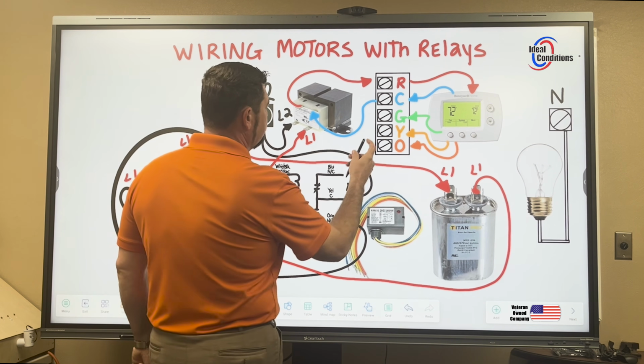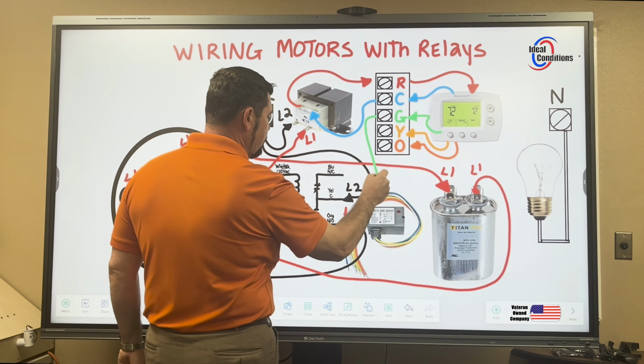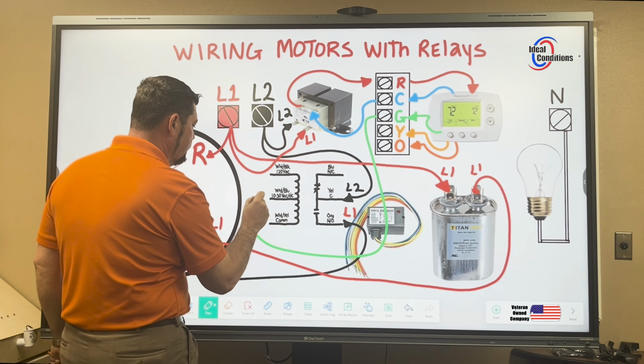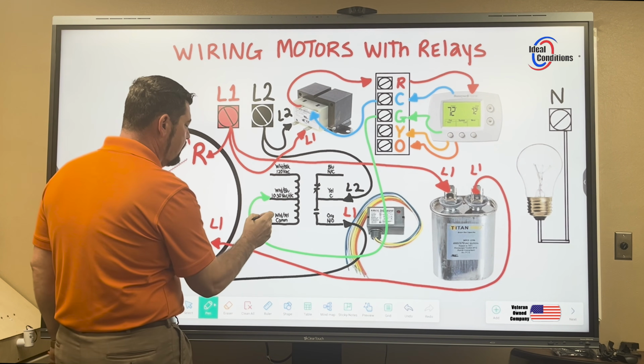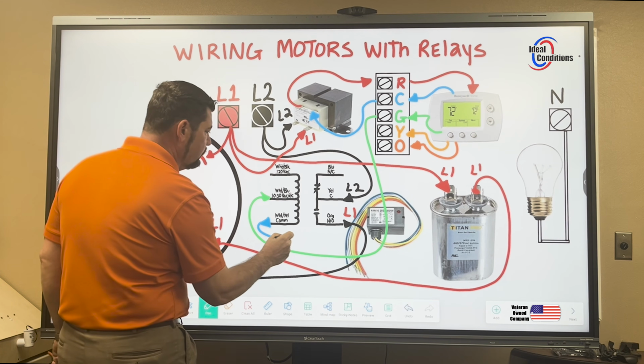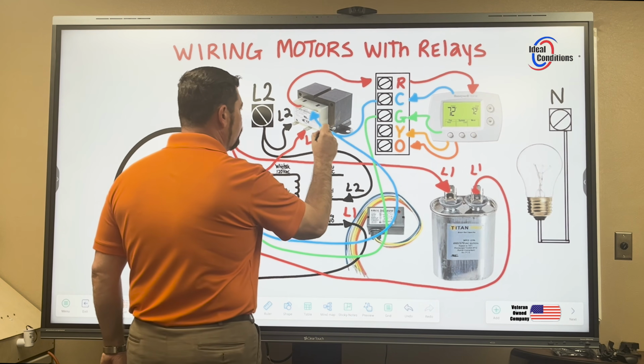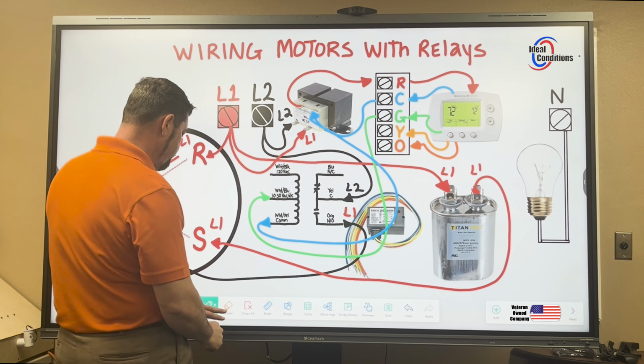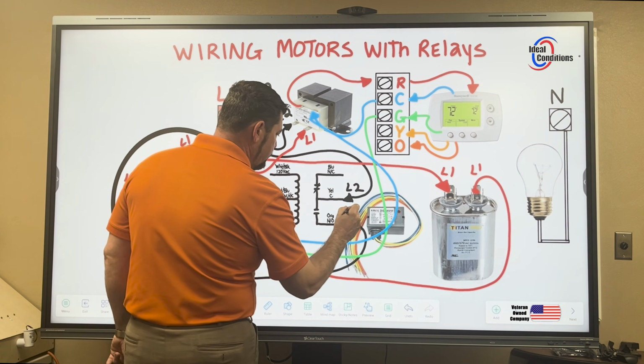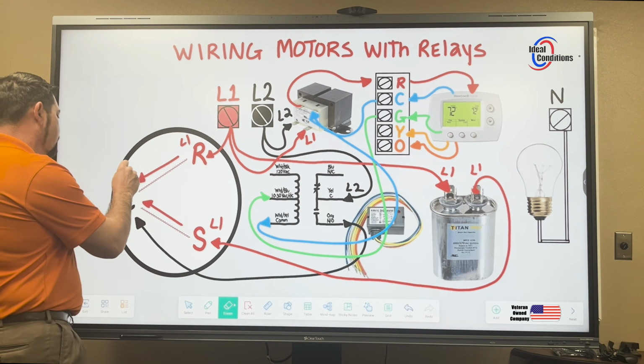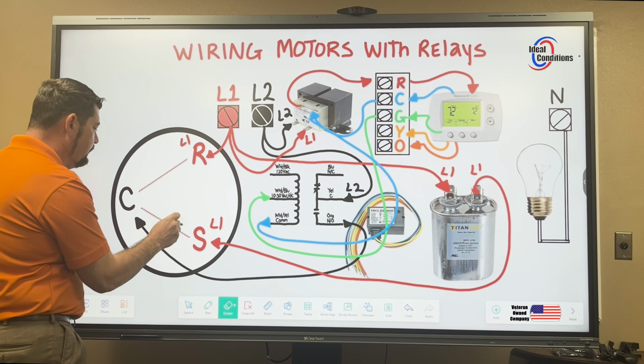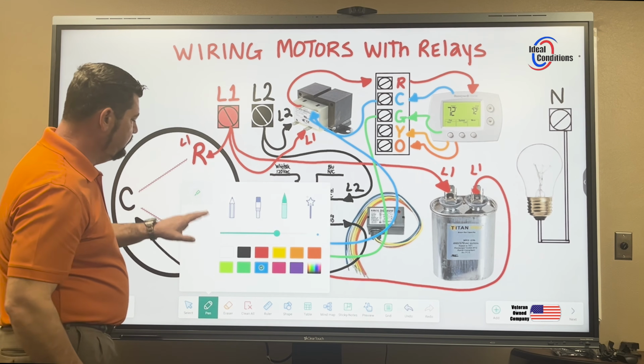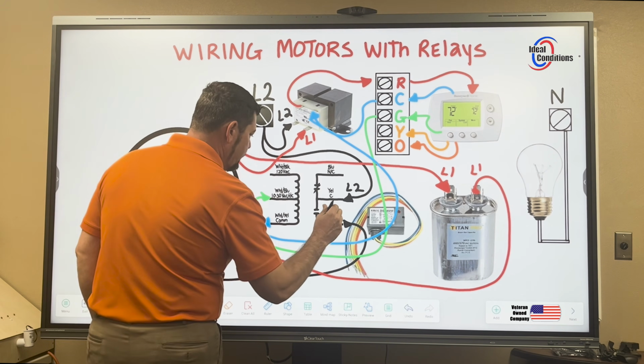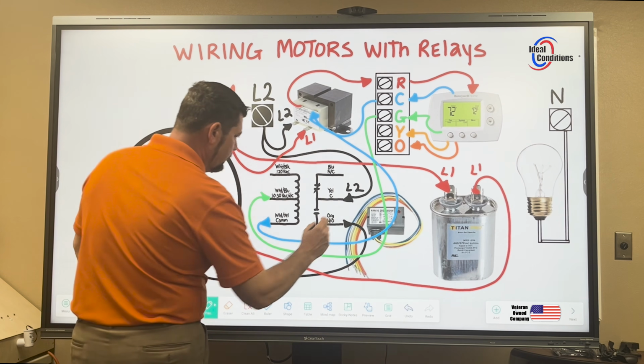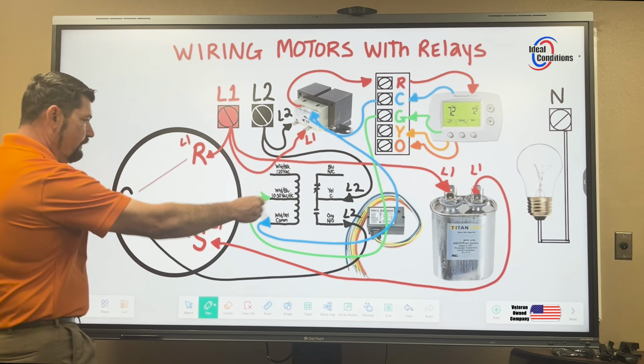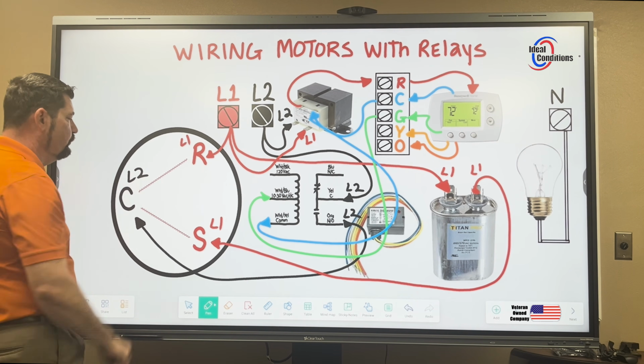We're going to say that the G call comes in, energizes the coil, common back out gives me a path back to my transformer, and at that point in time, L1 is no longer here, L1 is here, the path of electricity is no longer here, simply because now we have L2 present at this present time, and we have L2 present.